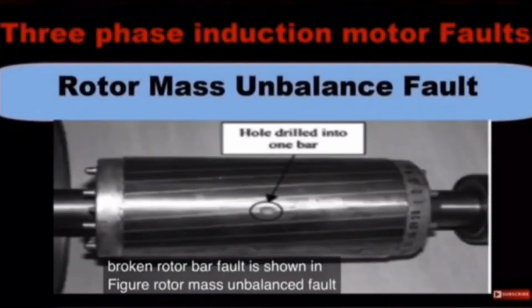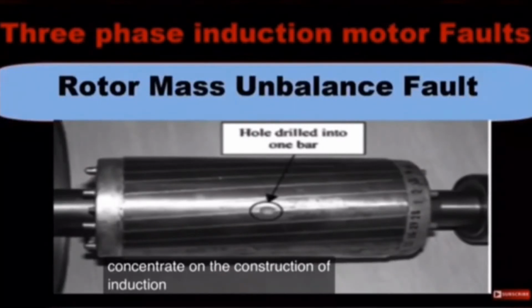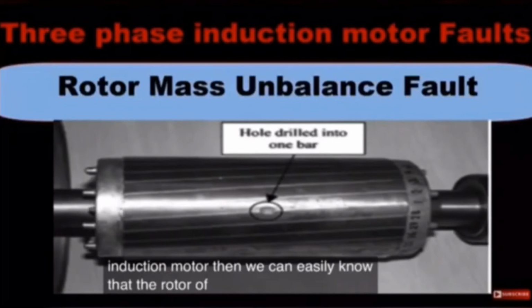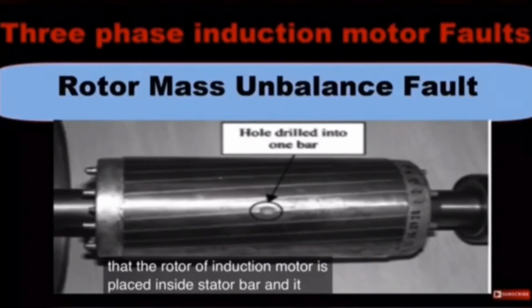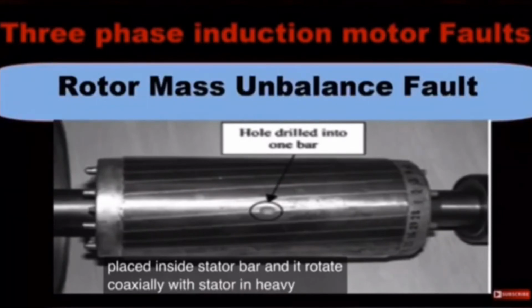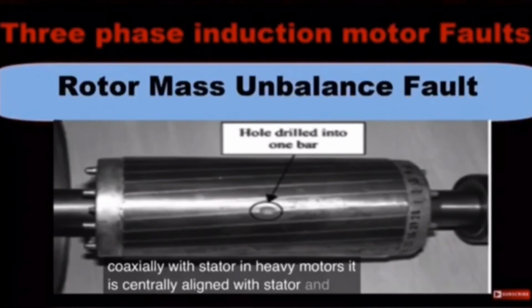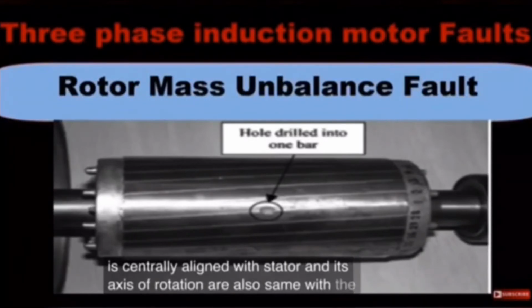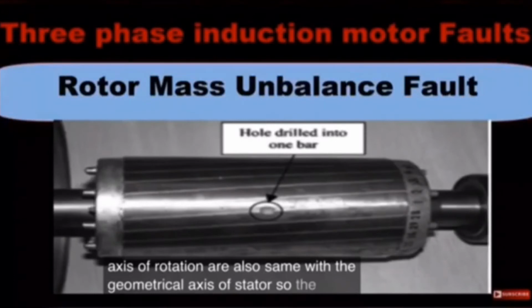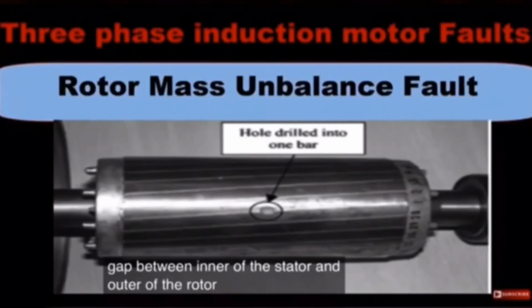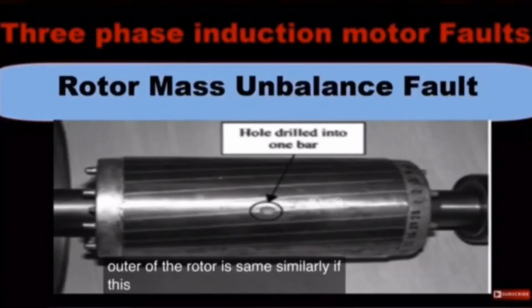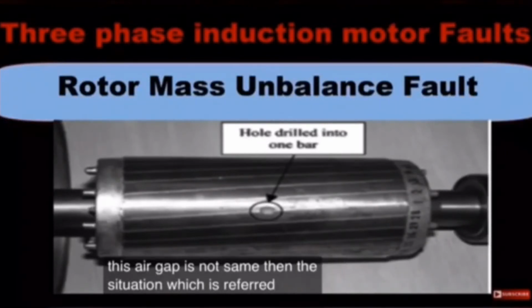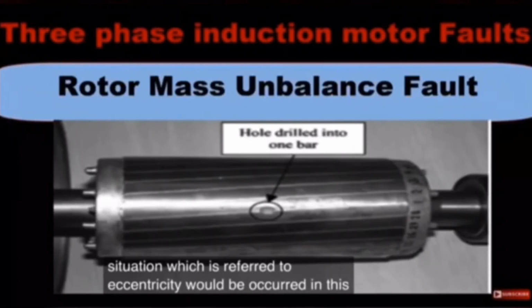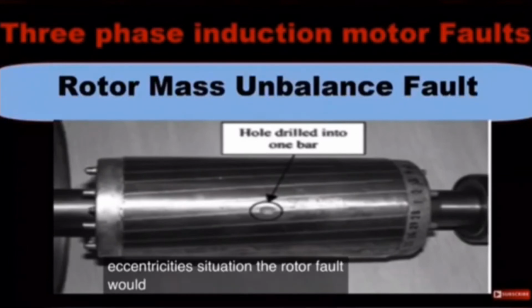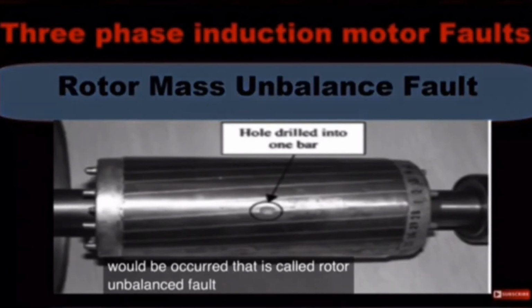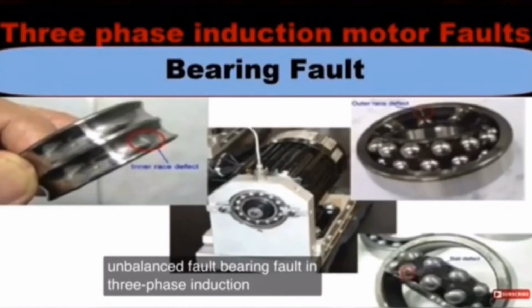Rotor mass unbalance fault. If we concentrate on the construction of induction motor, then we can easily know that the rotor of induction motor is placed inside the stator, and it rotates coaxially with stator. In heavy motors, it is centrally aligned with stator, and its axis of rotation is also the same as the geometrical axis of stator. So the air gap between inner of the stator and outer of the rotor is the same. Similarly, if this air gap is not the same, then the situation which is referred to as eccentricity would occur. In this eccentricity situation, the rotor fault would occur, that is called rotor unbalanced fault. Bearing fault. Environmental fault.